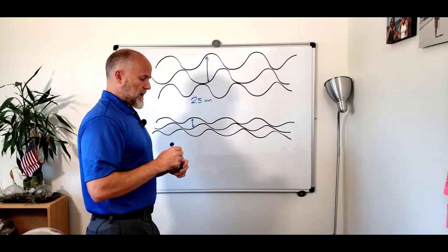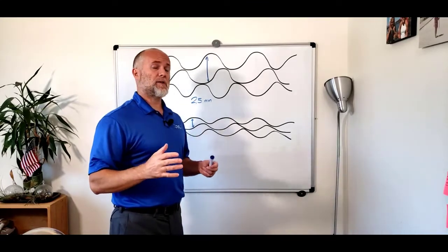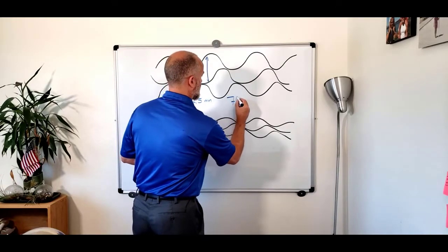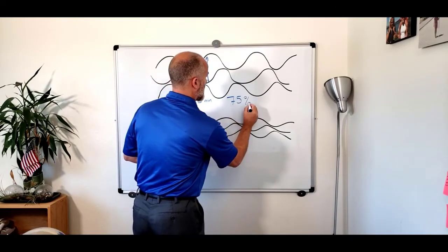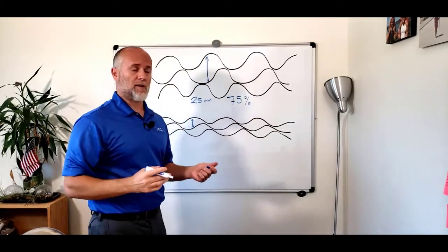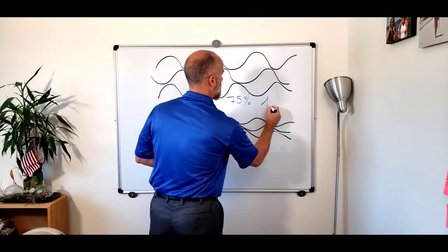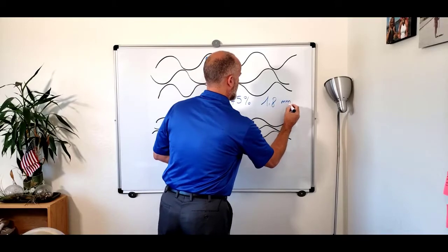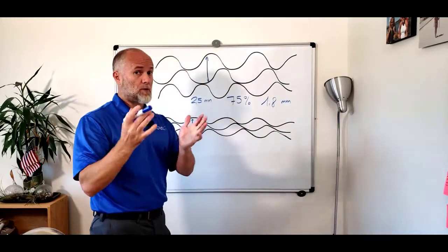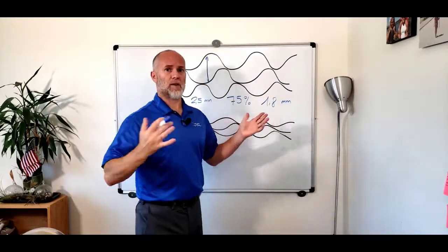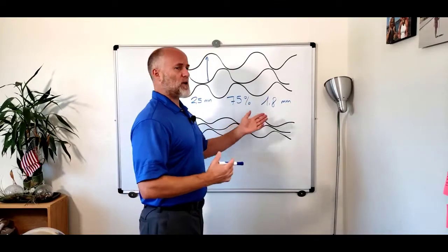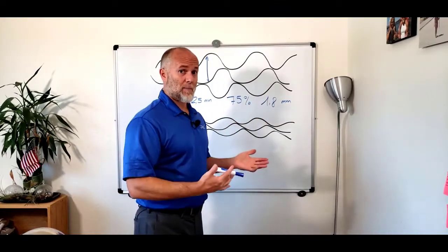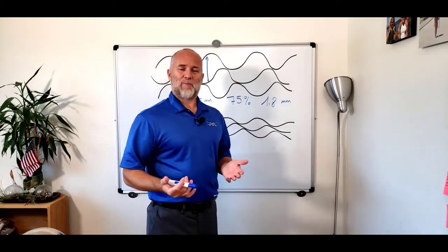We normally recommend that you don't have particles that exceed 75% of the size of the channels, which equals 1.8 and change millimeters. So once you know that you cannot have particles bigger than 1.8 millimeters going through your heat exchangers if you don't want them to build up, you of course design your mesh accordingly.